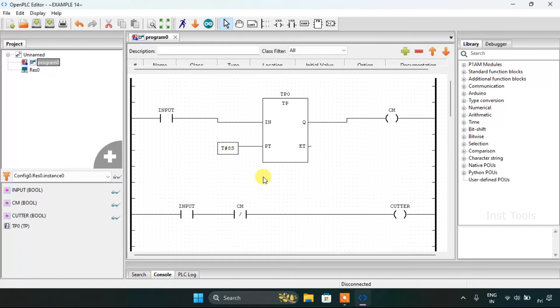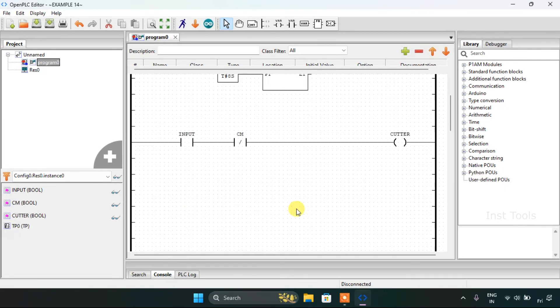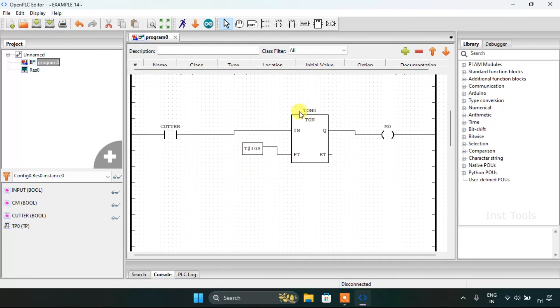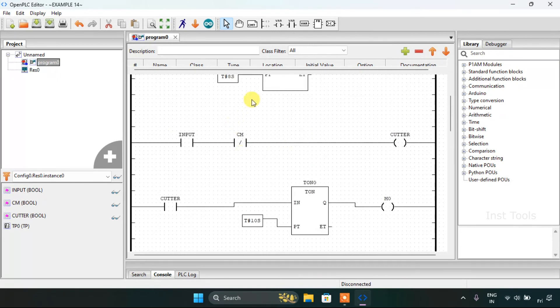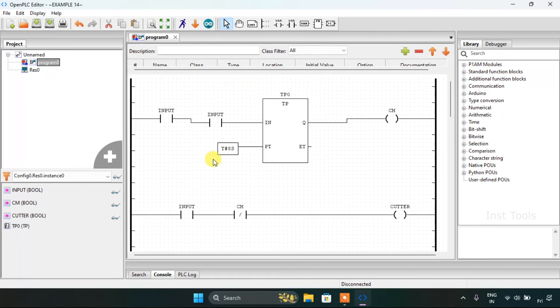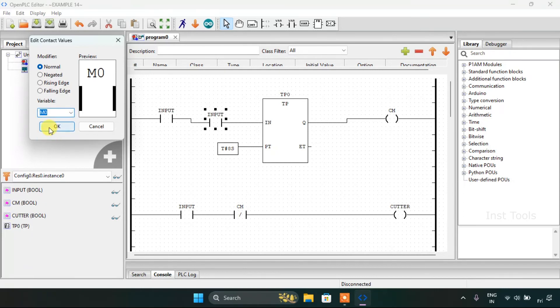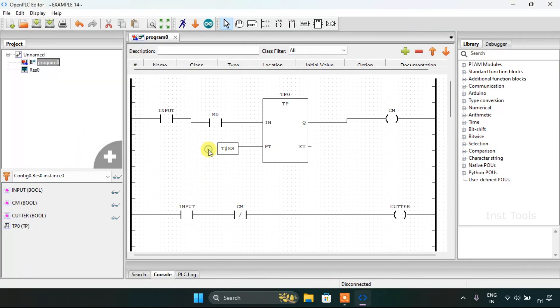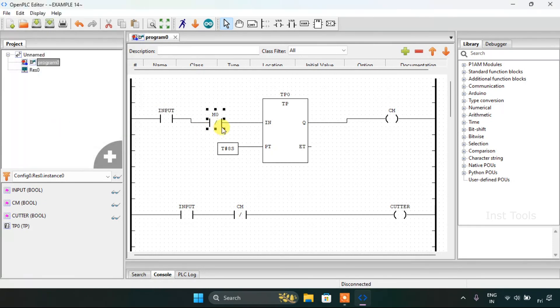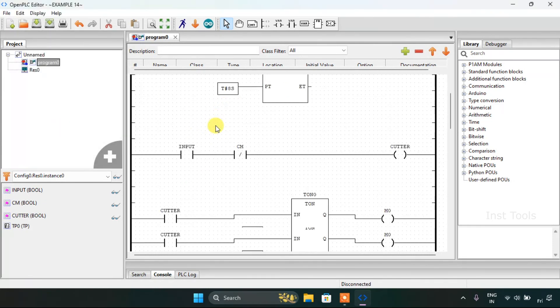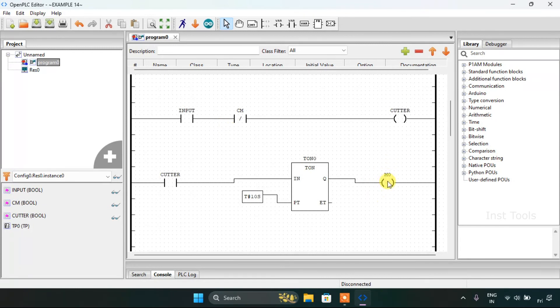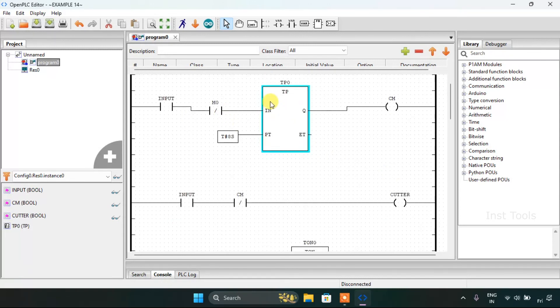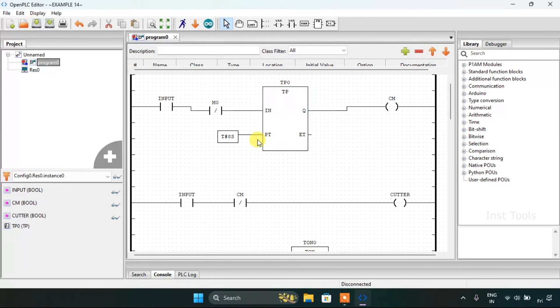And if you want to keep the whole function in a loop, you just need to create a memory bit and latch it here, the cutter, and then the pulse timer for some seconds. In order to keep this whole diagram in the loop, you just have to latch the normally closed memory bit here and use the cutter and use the TON function. When the cutter will go on, and after 10 seconds, M0 will go true. And with this, the TP function will be reset, and this whole function will be in a loop.